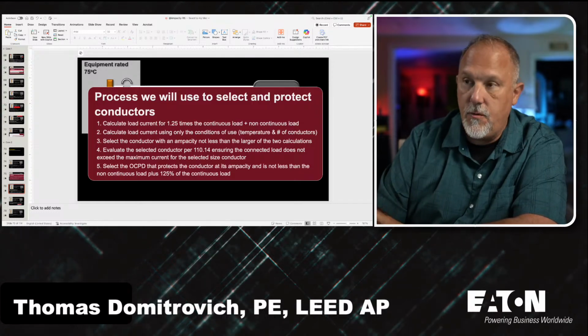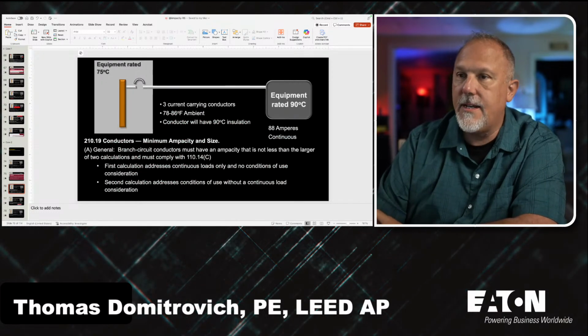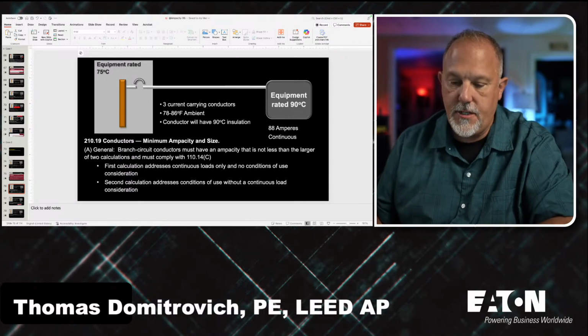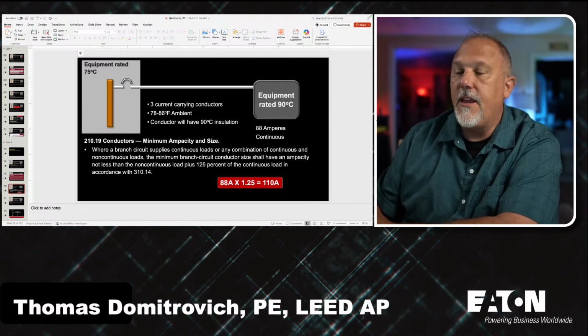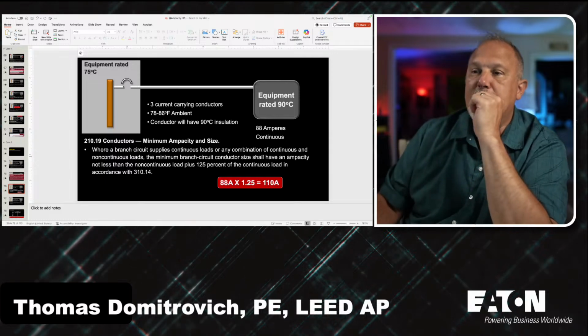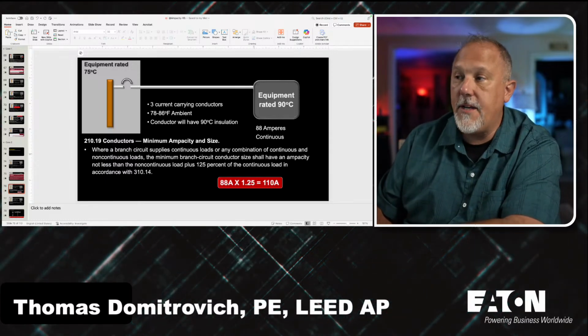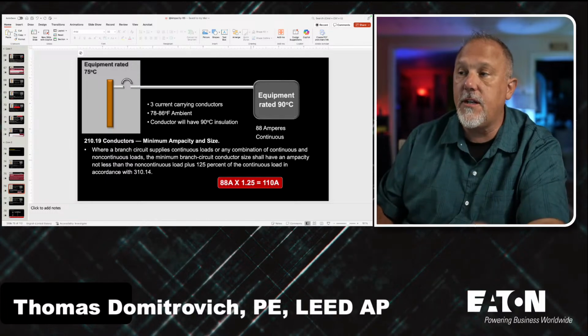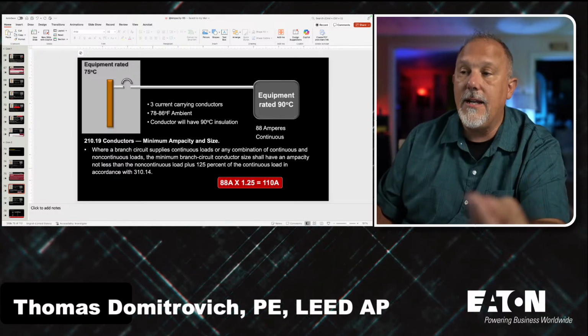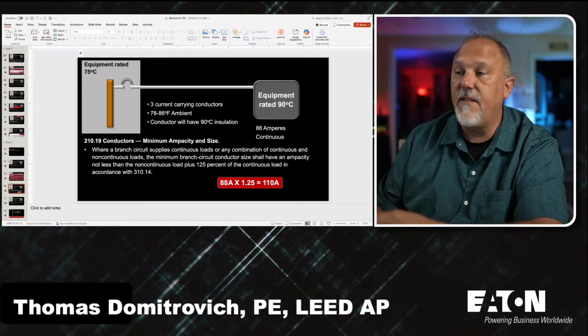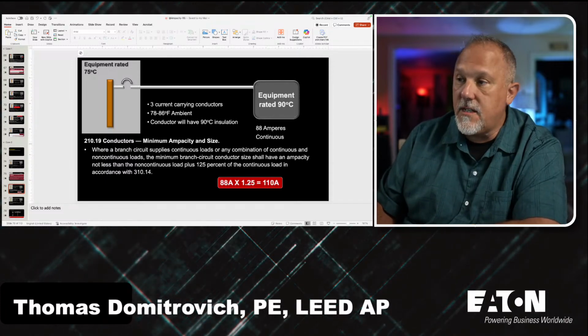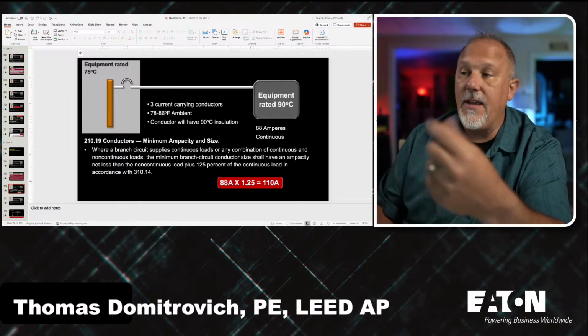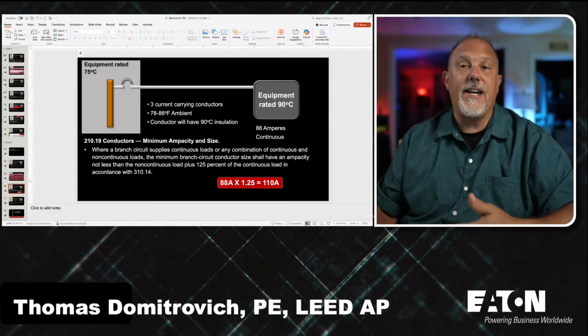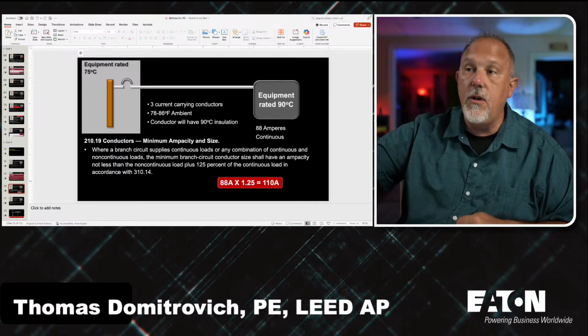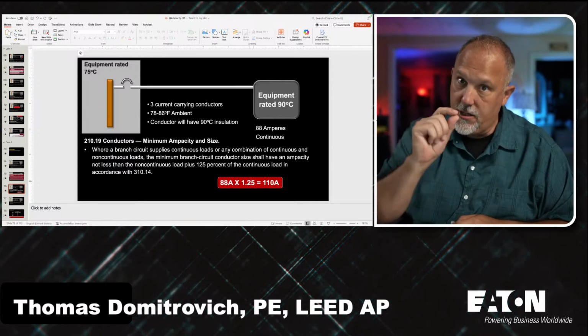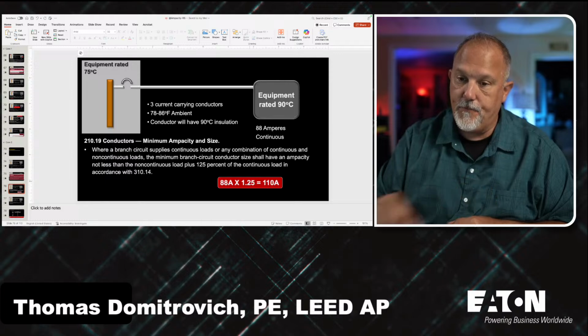All right, so the first thing I do, and I can delete this slide because I don't need it. It says where a branch circuit supplies continuous loads or any combination of continuous and non-continuous, the minimum branch circuit conductor size shall have an ampacity not less than the non-continuous load plus 125%. So all of this is continuous, so 88 times 1.25 is 110 amps. So I've satisfied the first calculation. I don't do the conditions of use. I just do the 1.25. Excellent.